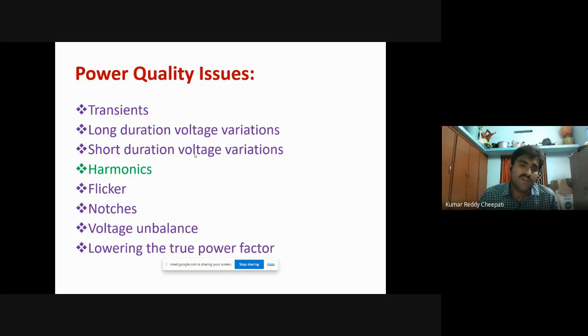Similarly, we have flicker, one of the power quality issues. Flicker is mainly due to the usage of conventional fluorescent lamps, so it is also termed light flicker. And notches are also a very important power quality issue. Because of notching, we can find various different amplitudes in a single or multiple cycles. And voltage unbalance. Our ideal power system is expected to be balanced in nature, but sometimes the three phases R, Y, B may get unbalanced in terms of phasor and also in terms of their amplitudes. Because of voltage unbalance, the flow of neutral current increases. Due to that, the neutral conductor gets heated up. And another power quality issue is the lowering of the true power factor. Due to the exponential use of lagging loads and also nonlinear loads, the power factor becomes less than 1. If the power factor is less than 1, it leads to many losses in the power system.